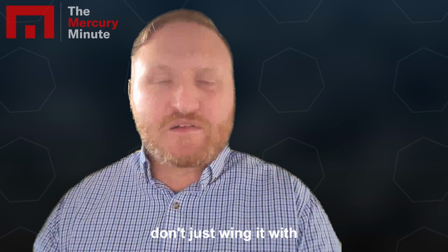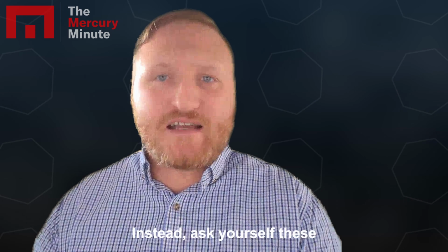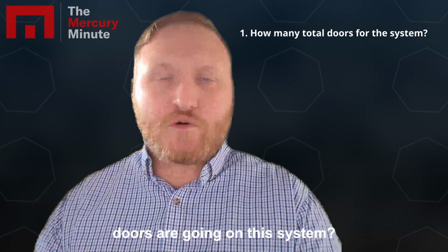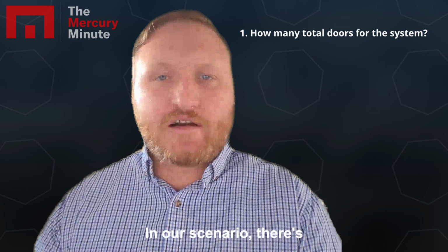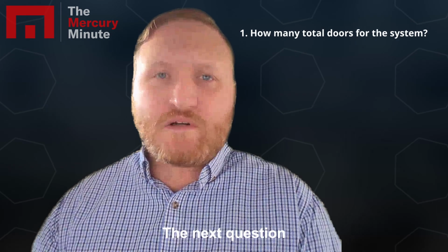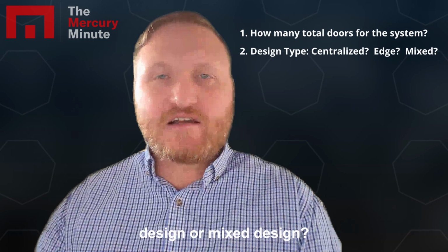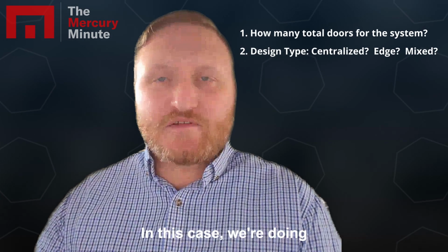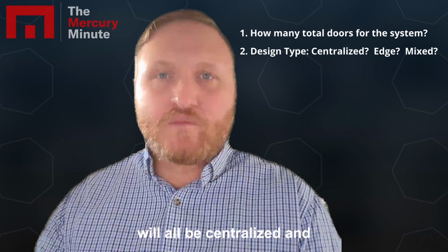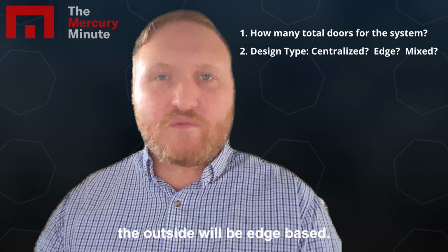Now, here's the real takeaway. Whenever building a BOM, don't just wing it with a whiteboard and hope. Instead, ask yourself these 4 critical questions. Number 1, how many total doors are going on this system? In our scenario, there's a total of 23. The next question is to ask yourself, is it a centralized design, an edge-based design, or a mixed design? In this case, we're doing mixed. The inside of the building will all be centralized, and the outside will be edge-based.